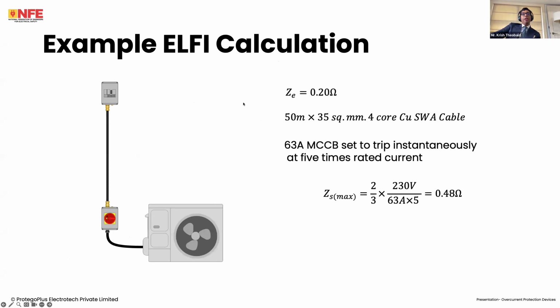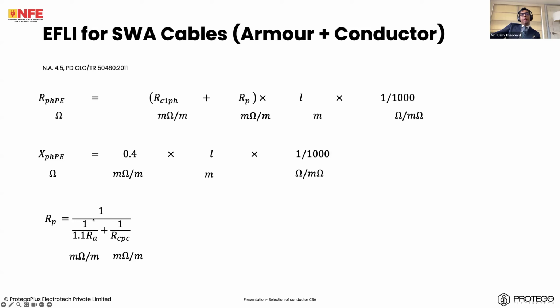RP, which is the effective resistance of the armor in parallel with the parallel conductor, is calculated by 1 divided by 1 upon 1.1 RA, which is the armor, plus 1 upon R of the protective, this is the parallel conductor. The 1.1 value is only multiplied to the resistance of the armor. That was the mistake that was here, by the way. 1.1 has to only be multiplied by the resistance of the armor. And like I said, instead of 0.3, we take 0.4 here as the reactive component.